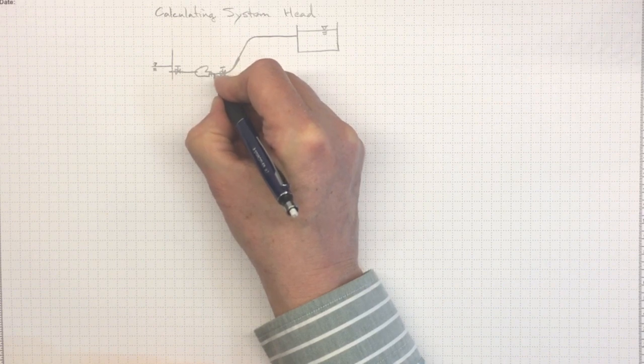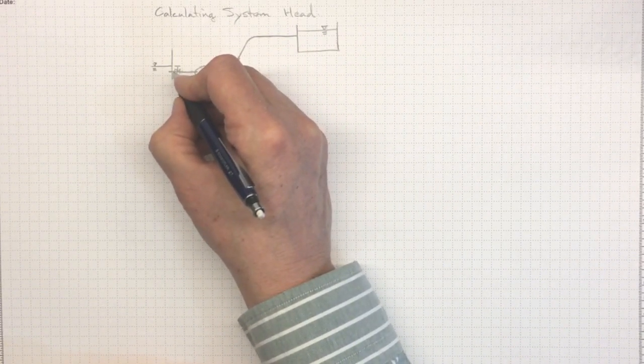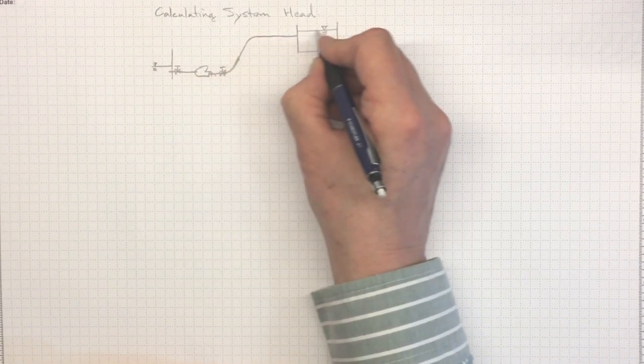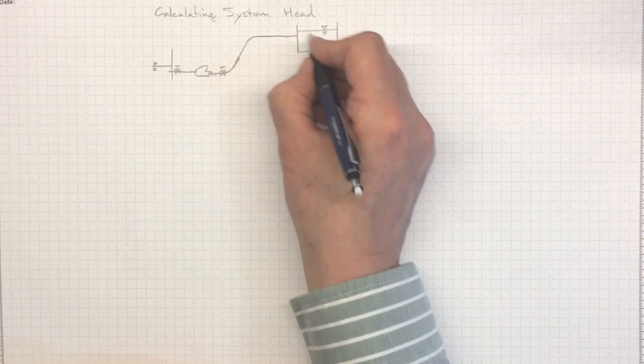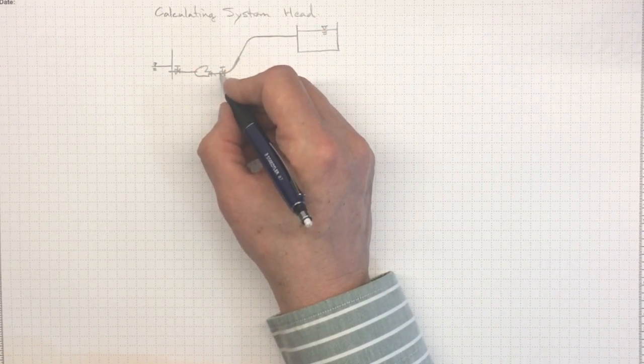And at the outlet of the pump, we really should have a swing check valve. That's a valve that'll prevent the flow from going backwards through the pump in case the pump turns off. Once we pump stuff up to the top of the hill, if we just shut off the pump, we don't want it to all flow down the hill again, backwards through the pump.